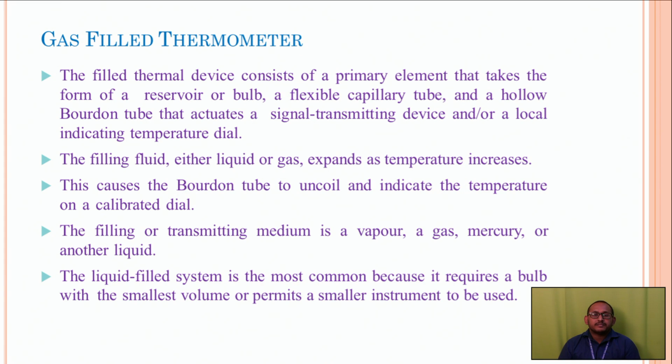The filling or transmitting medium can be a vapor or a gas, and it can also be another liquid. The liquid filled system is the most commonly used, because it requires a bulb with the smallest volume, which permits a smaller instrument to be used.